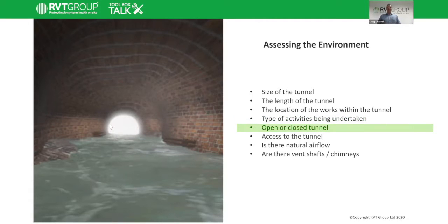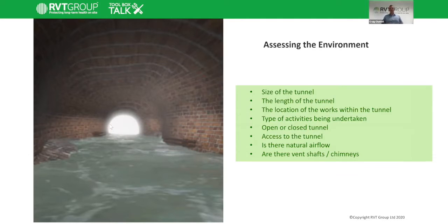Is the tunnel open both ends, or is it closed? Is it only open one end? What is the access like? How easily can you access the tunnel? Is there a natural airflow? Is there a prevailing wind flow through the tunnel? And what about shafts, vent shafts or chimneys? All these factors are really important. They can all impact and affect the effectiveness of a temporary ventilation solution.